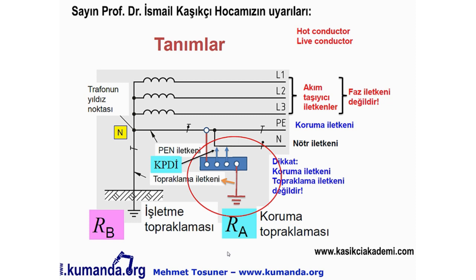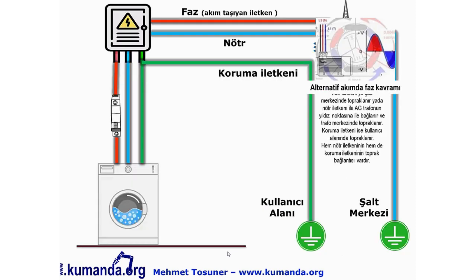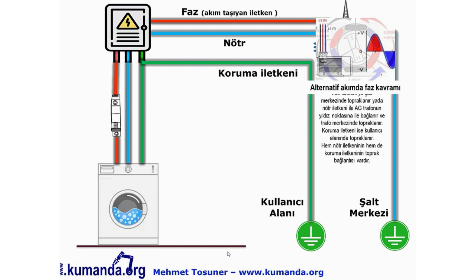Ya da eğer bir eş potansiyel barası ya da topraklama baramız varsa, bu baradan toprağa — toprağa çaktığımız kazıklara — yapılan bağlantı topraklama iletkenidir. Şebekeden faz ve nötr gelir; koruma iletkeni kullanıcı alanında yapılan topraklama bağlantısıdır. Şebekenin tipine bağlı olarak nötr iletkeni ya şalt merkezinde topraklanır ya da AG trafosunun yıldız noktasına bağlanarak trafo merkezinde topraklanır. Koruma iletkeni ise kullanıcı alanında topraklanır.